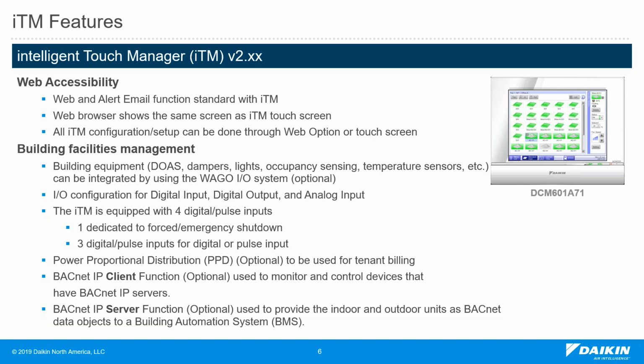And the Wago IO system is more scalable, so you can add more nodes, you can add more contacts to the Wago system. So that's good, because it's a very scalable, very flexible system that can tie into the ITM, and the user can look into all the different building equipment. Plus, the ITM itself has 4 digital pulse inputs, which could be used for the PPD function, or it could be used as a digital input to the ITM. So the first one is always dedicated as an emergency stop, and the other 3, DI2, 3, and 4, could be used as pulse input or digital input. So basically, if you want to monitor a door contact or one of the indoor units, you can connect that directly to the ITM.